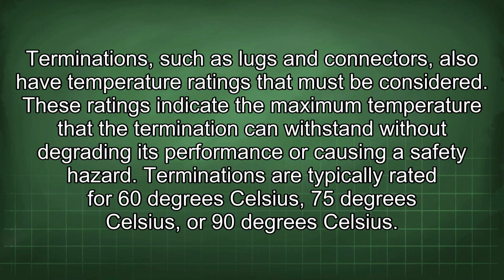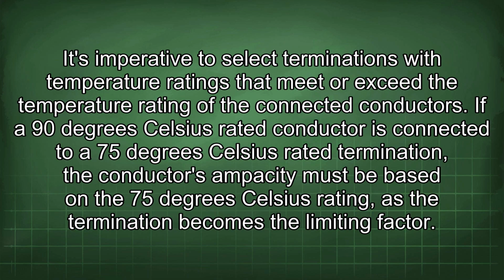Terminations, such as lugs and connectors, also have temperature ratings that must be considered. These ratings indicate the maximum temperature that the termination can withstand without degrading its performance or causing a safety hazard. Terminations are typically rated for 60 degrees Celsius, 75 degrees Celsius, or 90 degrees Celsius. It's imperative to select terminations with temperature ratings that meet or exceed the temperature rating of the connected conductors. If a 90 degrees Celsius rated conductor is connected to a 75 degrees Celsius rated termination, the conductor's ampacity must be based on the 75 degrees Celsius rating, as the termination becomes the limiting factor.